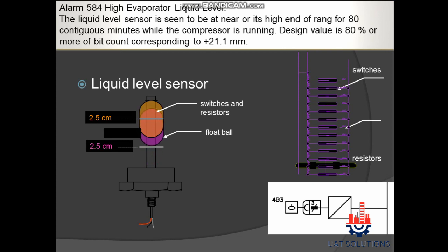Alarm 584 — High Evaporator Liquid Level: This alarm is shown when the liquid level sensor is seen to be at or near its high end of range for 80 contiguous minutes while the compressor is running.